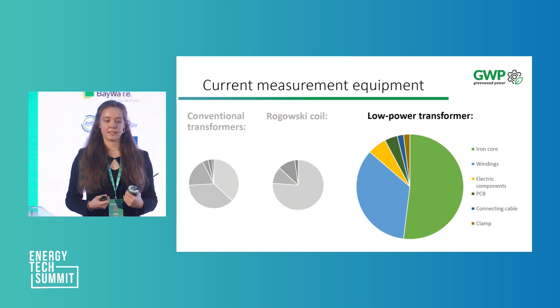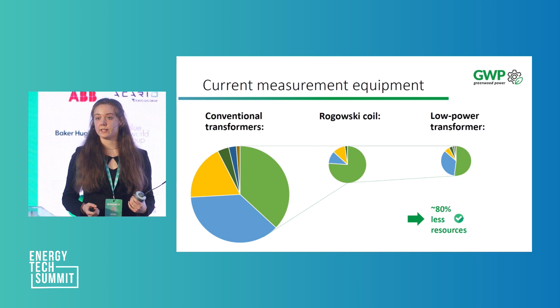For the Rogowski coil, this changes because the windings are way more, since you have an air core and you have to bundle up all the magnetic field lines somewhere. Now, in comparison, the low-power transformer still has the iron core, but since it's a much smaller product, you save 80% of all the resources compared to the other products.